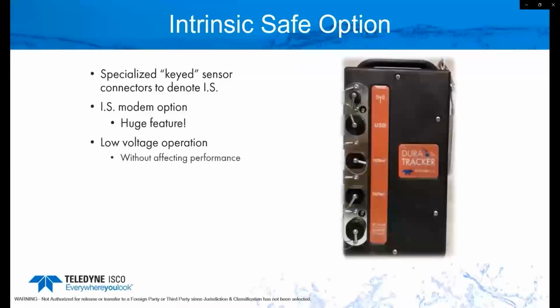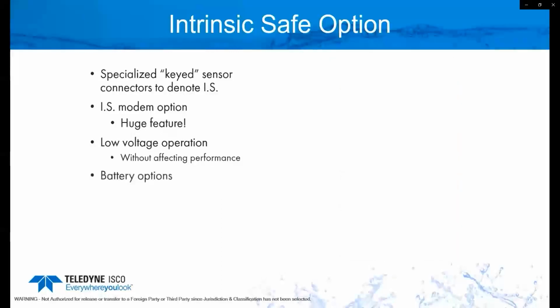All while still complying with the Class I Division I requirement for low voltage operation. So another big one we get asked a lot: if you go intrinsic safe, are you limiting the power to your sensors? Will it affect the accuracy or the range? The answer is no. It doesn't affect the accuracy, it doesn't affect the limits or range of the sensor. Everything performs exactly as it would, whether it's intrinsic or not.